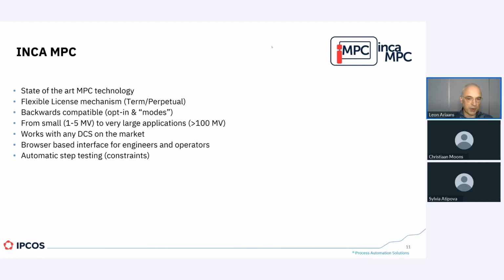We include support for automated step testing. We do modeling based on data that we collect from the plant, from the unit from MPC. While collecting that data, it's important that steps are applied to the process so that we can see how it responds to those steps. Those steps can be applied manually, but you can also ask INCA MPC to do that for you.